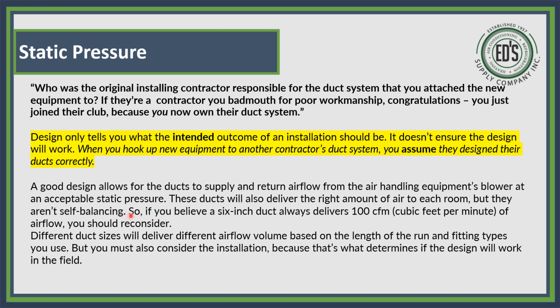One thing I see a lot of is contractors come in and buy 6-inch flex, assuming they need 100 CFMs in a bathroom or a small bedroom. They'll get 6-inch flex and a 4x10 by 6 boot and a 4x10 floor grill. That 4x10 grill only lets 55 CFMs come through. So you've already created static pressure right there, because it's not going to let the whole 100 come through. You're going to hear it whistling or hear airflow coming through because the velocity speeds up. So you think, okay, well, that velocity is great, but not if it's self-inflicted like that. If you have designed the duct to have the exact same CFM or the right carrying capacity, you will automatically have good velocity. But when you start restricting it down too far, you're going to cause back pressure on the blower motor. So you've got to keep that in mind.